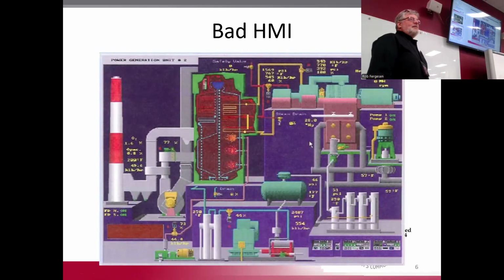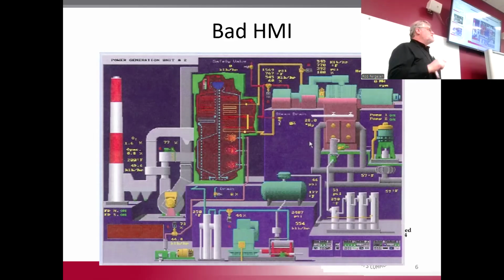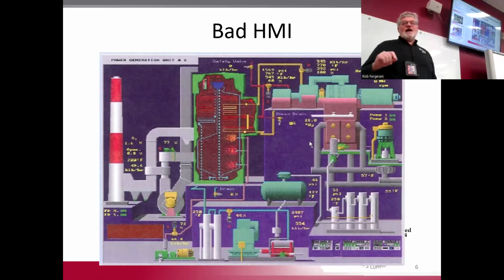It's pretty. But what happens if something goes wrong? This whole thing has tiny, tiny little indicators, so I've got to get really close to the screens. It's got a lot of data all over it. If I have an alarm situation, can I tell what the root cause is? No. It's got too much on the screen, too much crowded information. It doesn't have any logical way of tracing root causes.